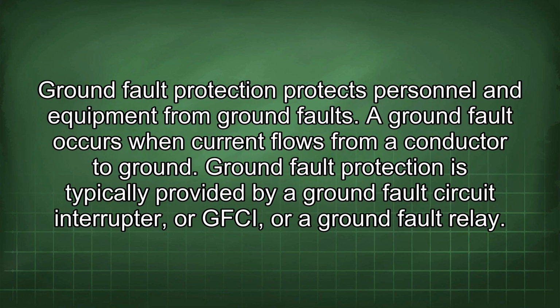Ground fault protection protects personnel and equipment from ground faults. A ground fault occurs when current flows from a conductor to ground. Ground fault protection is typically provided by a ground fault circuit interrupter, or GFCI, or a ground fault relay.